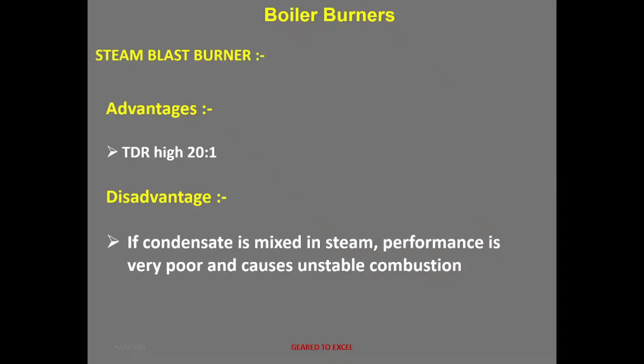Steam blast jet burner advantages and disadvantages. Advantage: high TDR of 20:1. Disadvantage: if condensate is mixed in the steam, performance is very poor and causes unstable combustion.